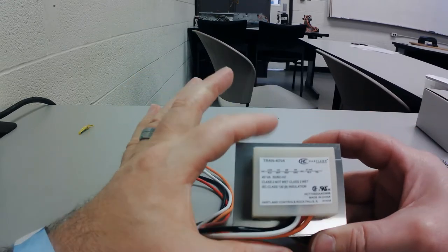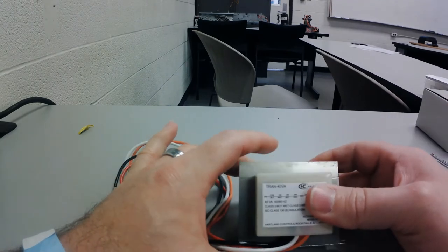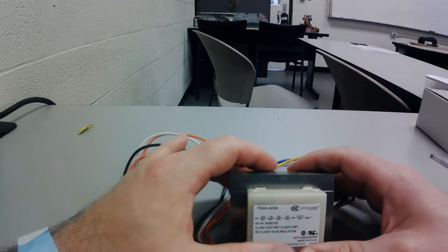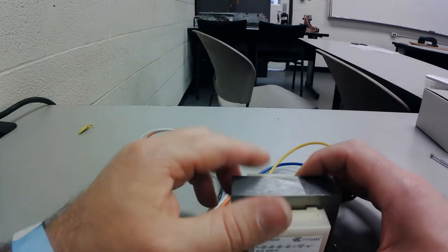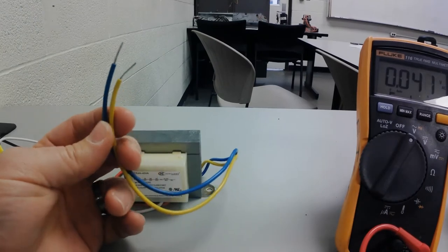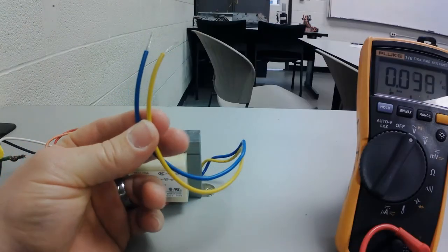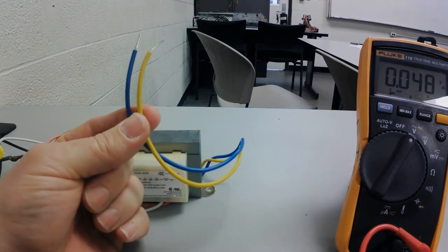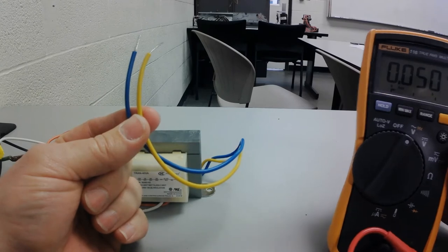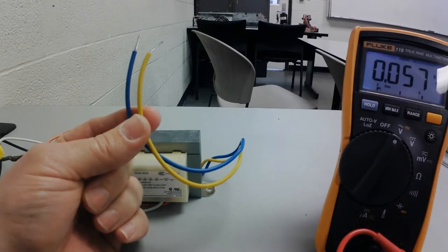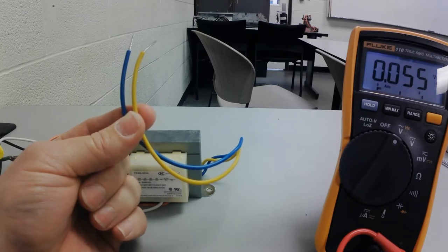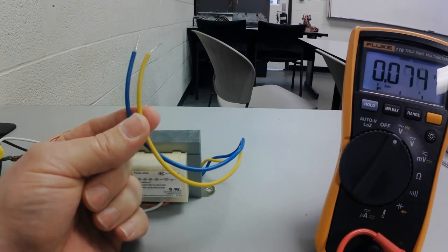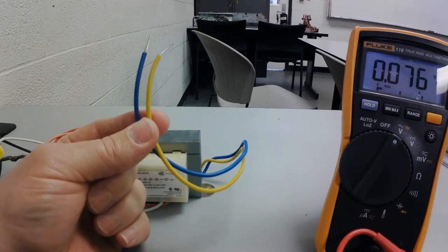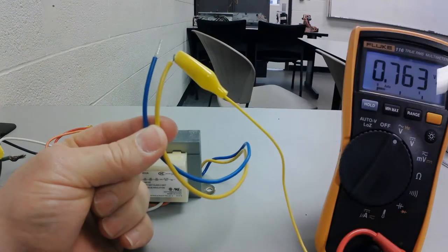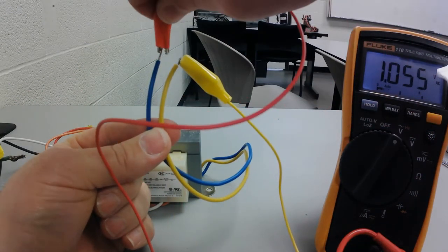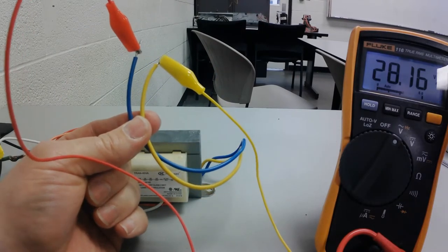So I'm sitting next to a 120 volt power source. I'm going to wire this up for 120 volts, and we're going to check its output, and then we're going to check the voltage on the other terminals. So hold tight, and I'll be right back. Okay, so I've got my 120 volts wired into the primary side, and I'm going to try to leave my multimeter here so you can see the voltage that I'm getting as we are going through these little checks. So I've got some wire nuts on the high voltage terminals that we're not using, and I'm going to use some low voltage alligator clips to connect to the secondary side. And you can see over here that I've got 28 volts.